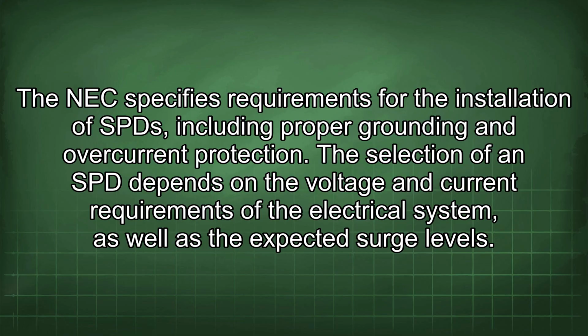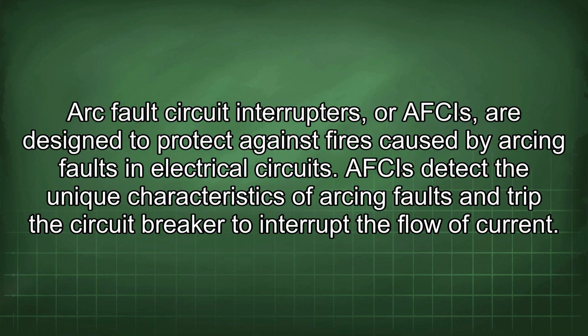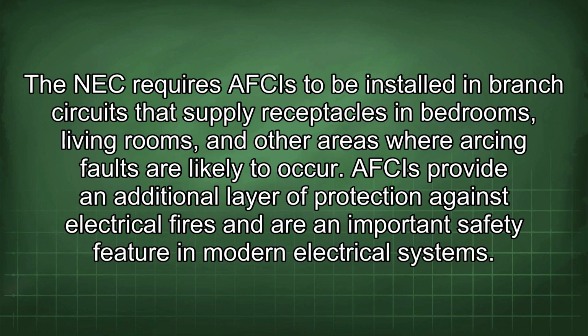The selection of an SPD depends on the voltage and current requirements of the electrical system, as well as the expected surge levels. Arc fault circuit interrupters, or AFCIs, are designed to protect against fires caused by arcing faults in electrical circuits. AFCIs detect the unique characteristics of arcing faults and trip the circuit breaker to interrupt the flow of current. The NEC requires AFCIs to be installed in branch circuits that supply receptacles in bedrooms, living rooms, and other areas where arcing faults are likely to occur. AFCIs provide an additional layer of protection against electrical fires and are an important safety feature in modern electrical systems.